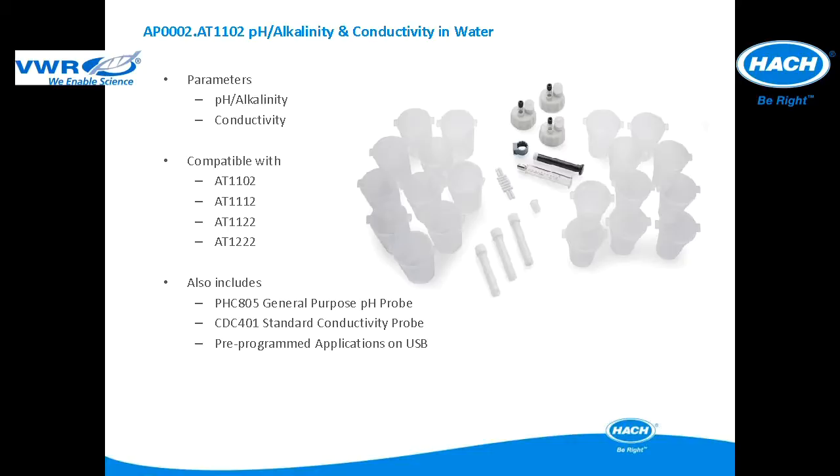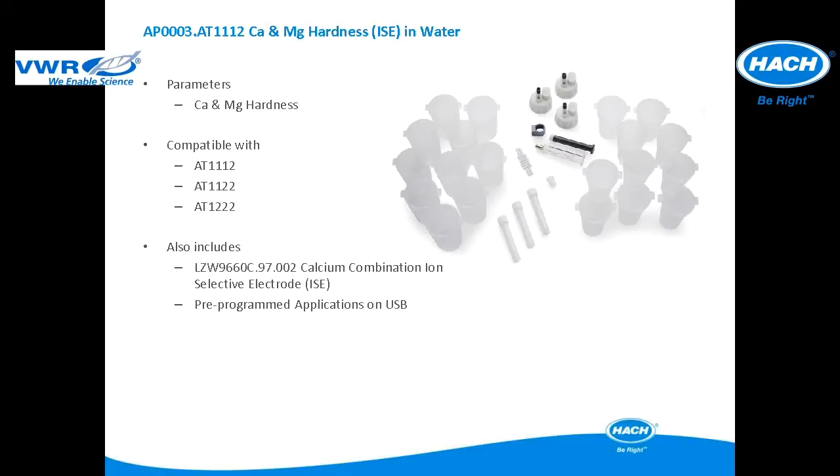The pre-programmed applications are included in a USB application key. This next application package is compatible with the AT1112, AT1122, and AT1222. It includes all of the items pictured and an LZW9660C.97.002 Sension+ calcium combination ion selective electrode. The pre-programmed applications are included in a USB application key.